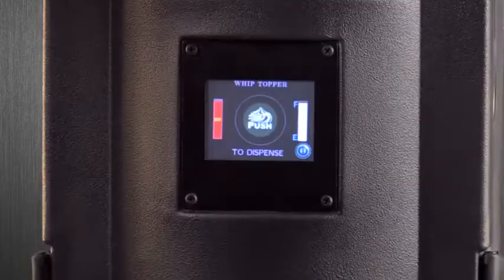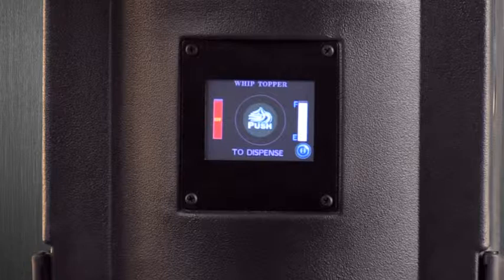Next, we'll be discussing issues with the machine that has high temperature. The unit is set up to operate within the temperature range of 33 degrees Fahrenheit as a low temp set point and 38 degrees Fahrenheit on the high temp set point. If the unit exceeds 60 degrees, the unit software will activate a temp alarm error that will be visible on the display and activate an audible alarm that will beep until it is resolved.